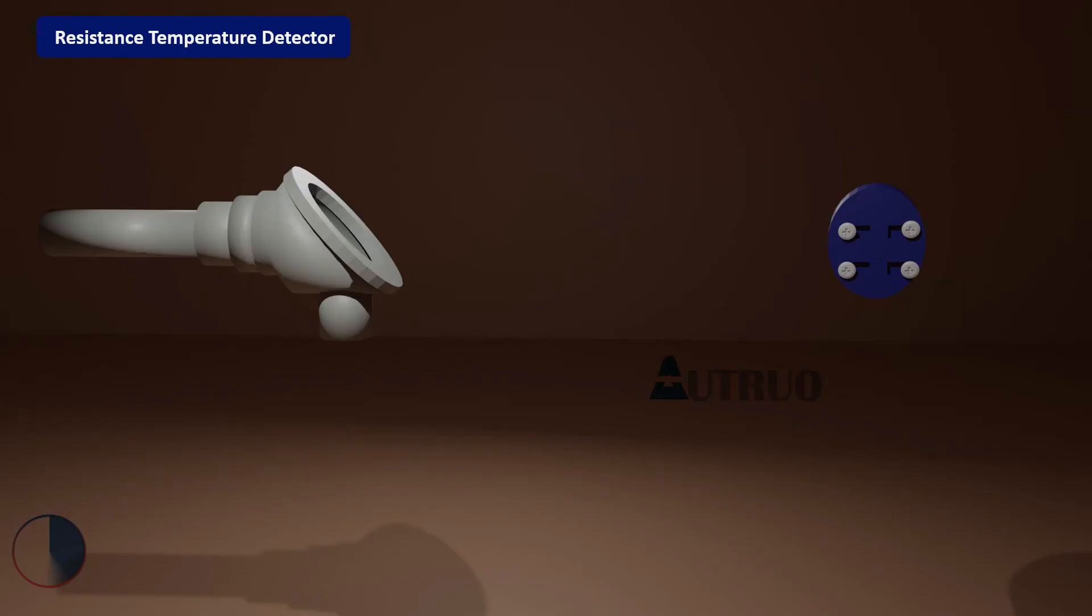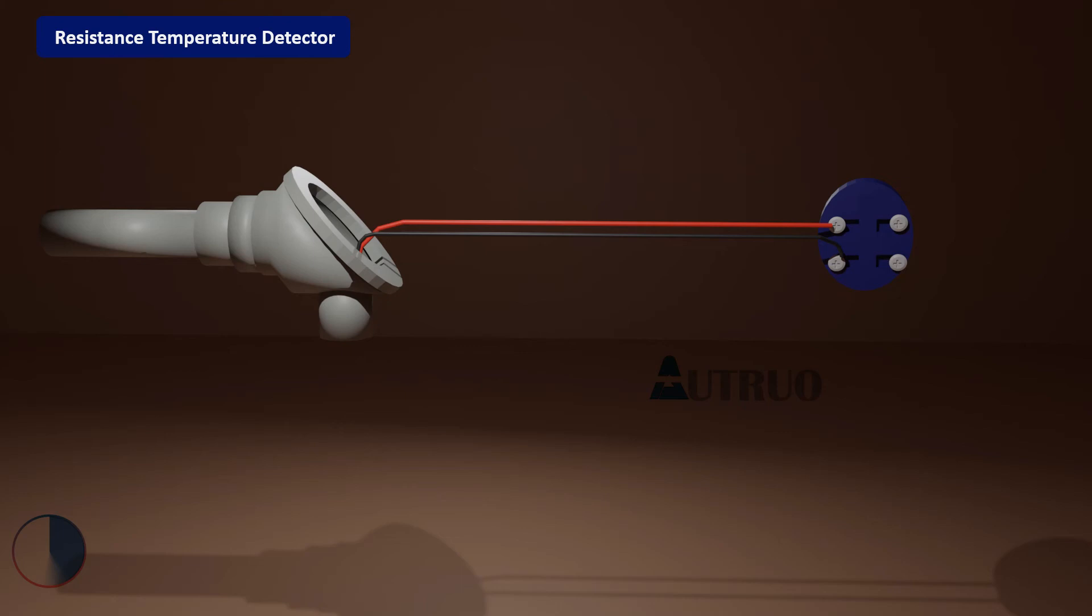Resistance temperature detectors are passive devices, which means they do not produce an output on their own. Instead, external electronic devices measure the resistance by passing a small electrical current through the sensor to generate a voltage—typically 1 or 5 milliamperes maximum without risk of self-heating. Passing too much current could lead to power dissipation and heat up the RTD.